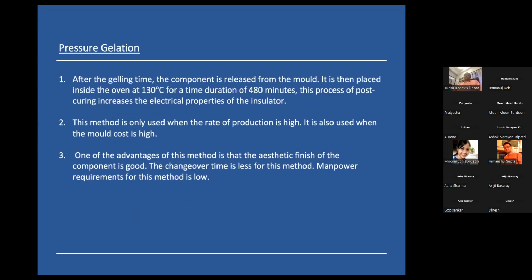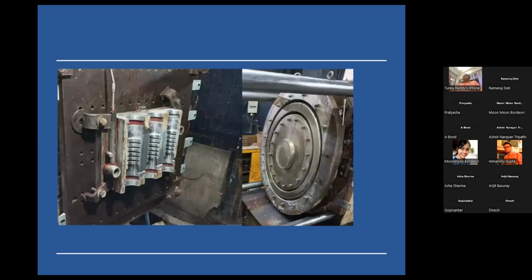Now after the gelling process, the component is released from the mold. Then it again has to undergo curing in the oven. The time duration for this is around 480 minutes. The curing process is important because it increases the electrical properties of the insulator. As I mentioned earlier, one of the advantages of pressure gelation over gravity casting is that the aesthetics of this method are quite good. Changeover time is very less, and the manpower requirements are also very less for this method.